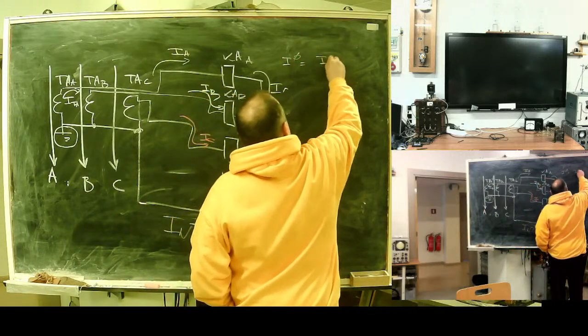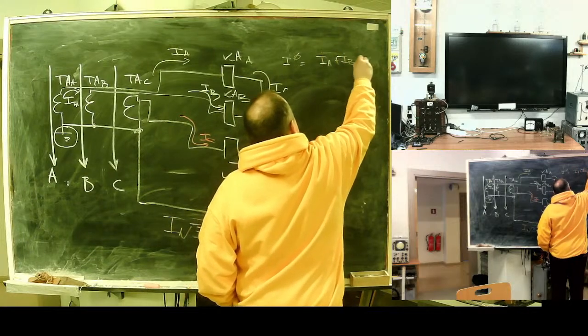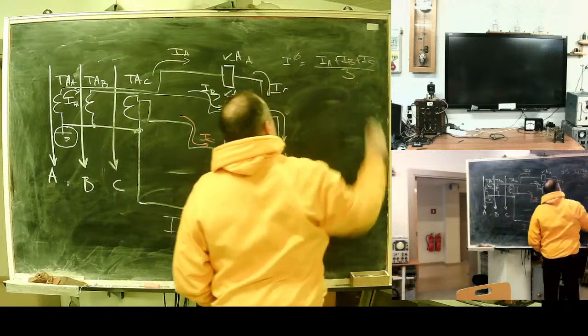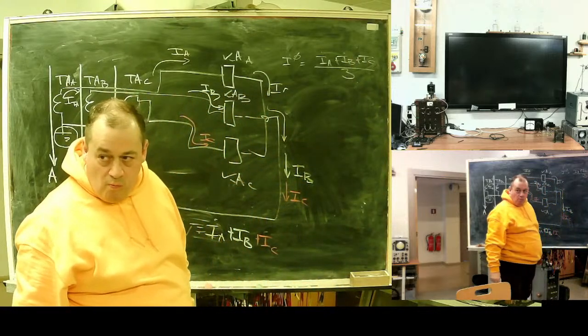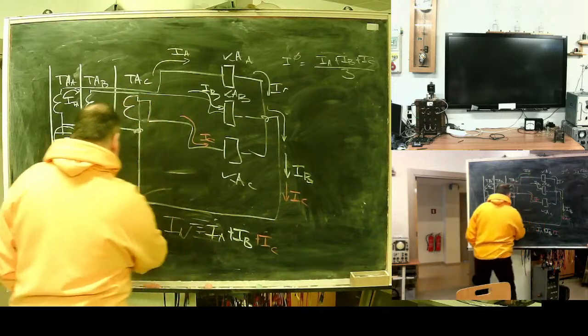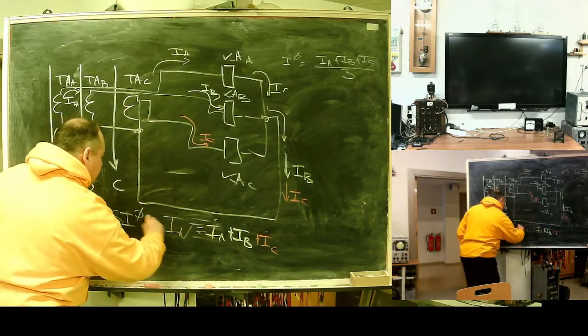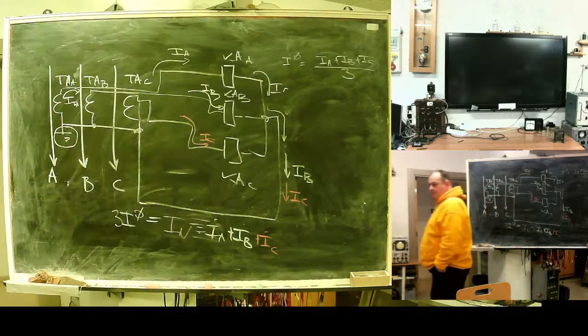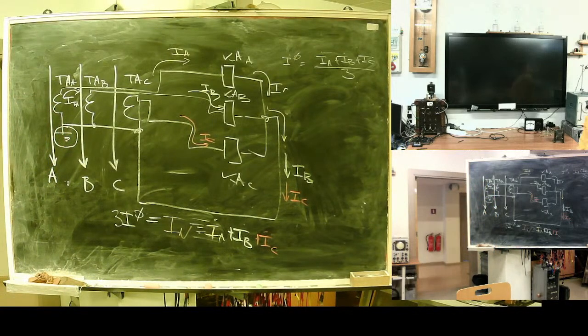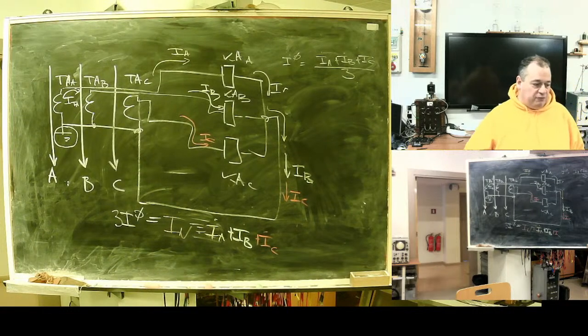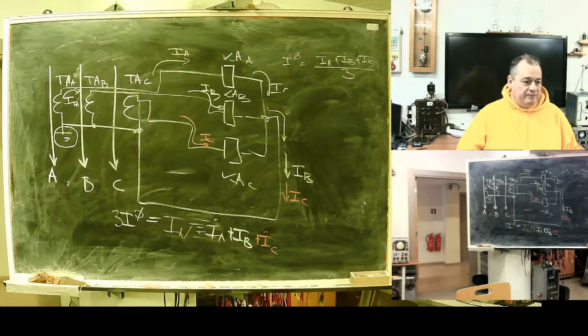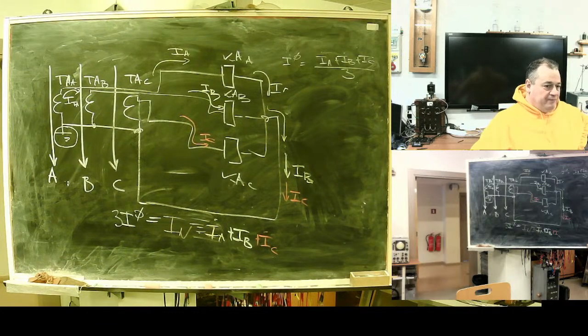Sequence current is IA plus IB plus IC divided by 3. So this one is a triple zero sequence current. If we do see a zero sequence current, what's the first idea when zero sequence current appears? We have Earth's fault. The first thing we should talk about if we see zero sequence current is an Earth's fault.